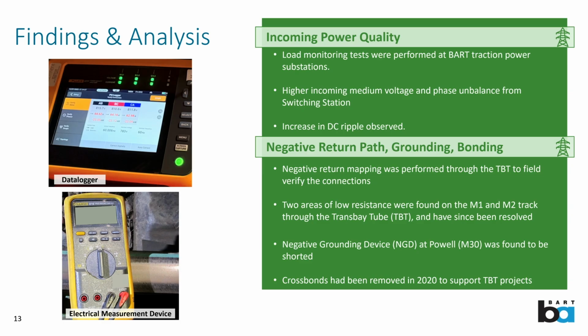So I should also explain what we mean by DC ripple. On a typical substation that has a 1,000-volt DC output, much like a DC battery, you'd expect that to be a constant voltage. But in practice, it does come with a small amount of ripple. That ripple is normal. These are 12-pulse rectifiers. And through the process to take AC and rectify it, it's never possible to completely eliminate that ripple. So on a 12-pulse, it's a 720 hertz ripple. And what we were looking at is, did that increase with all of the minor changes here and there? Did that DC ripple look different?